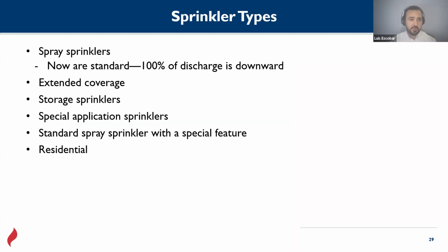Spray sprinklers. Now the standard is 100% of discharge is downwards. There's always a confusion. Well, not always, sometimes, right? When we speak about pendant and upright sprinklers, because of the orientation: the pendant is oriented downwards and the upright is oriented upwards, right? And at the very beginning, when I started in the industry, I used to think that the upright sprinklers released water to the ceiling, but obviously they don't, right? But it can be confusing sometimes.